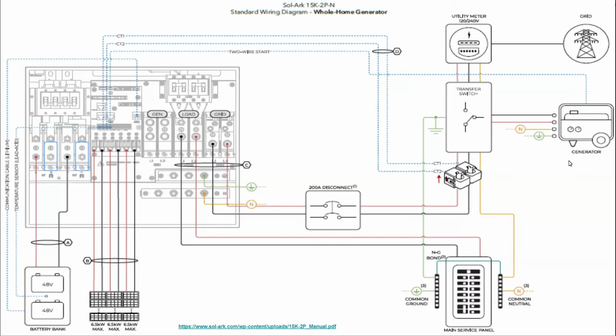The source, the grid or the generator, sets the frequency of the grid. And when you have a very large source like the size of the Mississippi River, your little small solar array can't impact it. When you have a source that is about the same size as your inverter, well, then backfeeding that source will impact things like the frequency or the voltage of the supply. And so when the Sol-Ark is used in this configuration, where you're utilizing a stationary generator with a generator's third-party external transfer switch, while the inverter does not have a contact or a relay to detect grid status, it'll detect the fluctuation of the grid voltage if it starts to sell back to the grid and say, "Oh, I'm backfeeding a generator. I need to stop that."